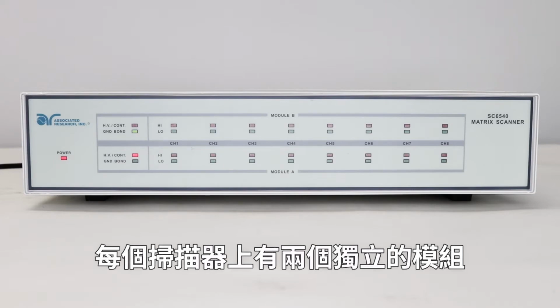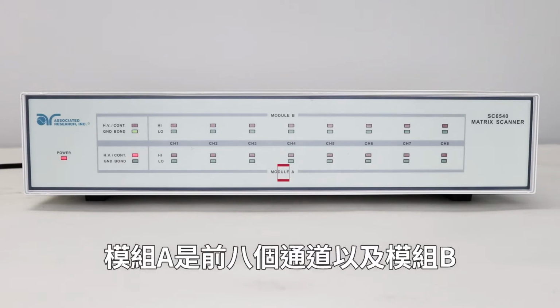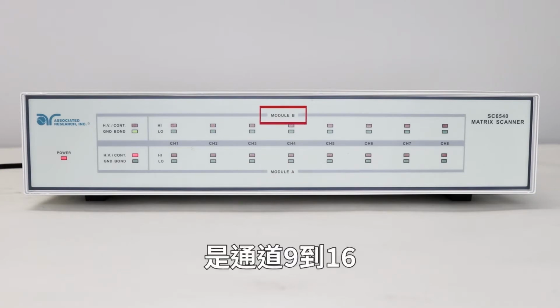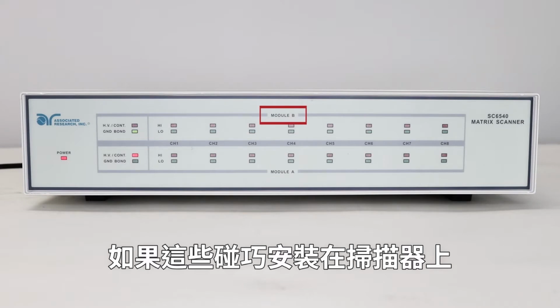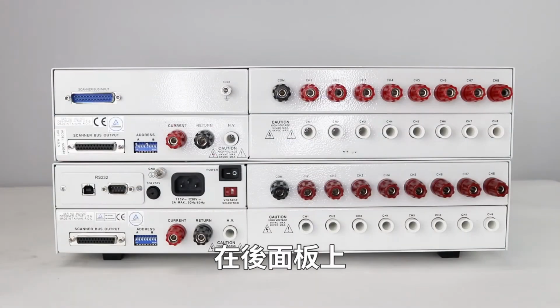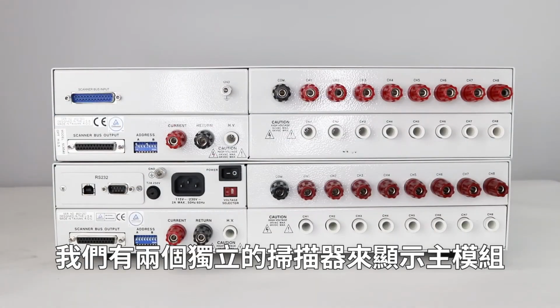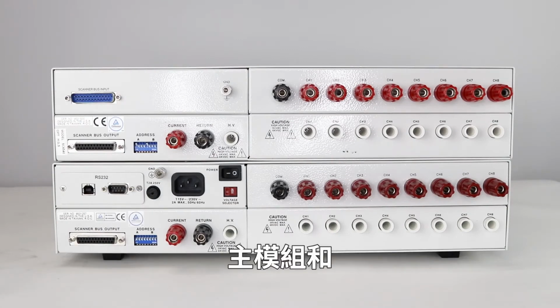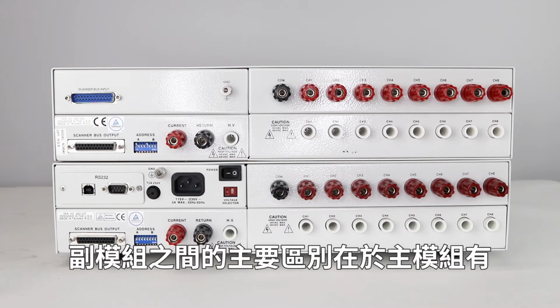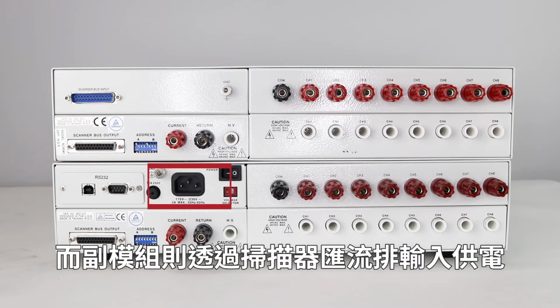There are 2 separate modules on each scanner. Module A, which is the first 8 channels, and Module B, which is channels 9 through 16, if those happen to be installed on the scanner. On the rear panel, we have 2 separate scanners to show the difference between a main module and a secondary module. The major difference between the main module and the secondary module is the main has its own input power, whereas the secondary draws power through the scanner bus input.